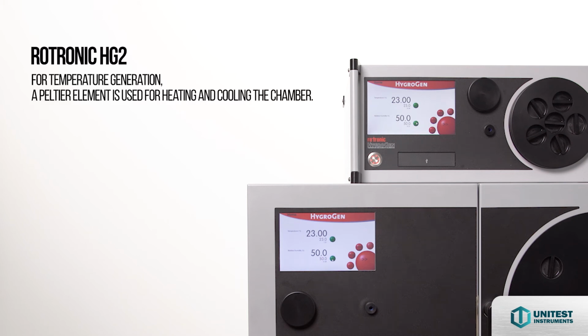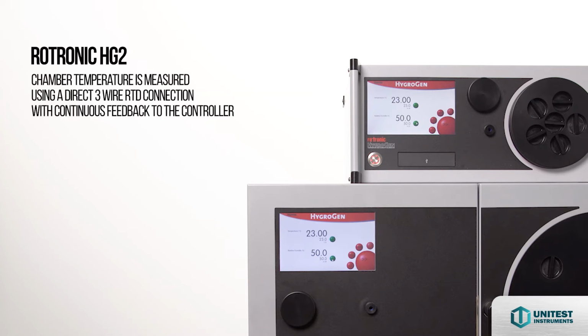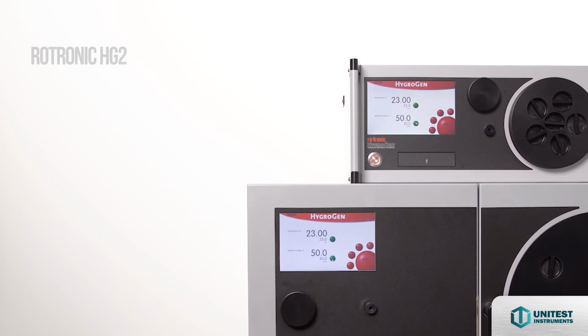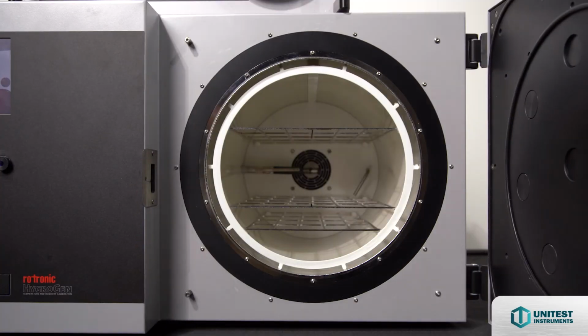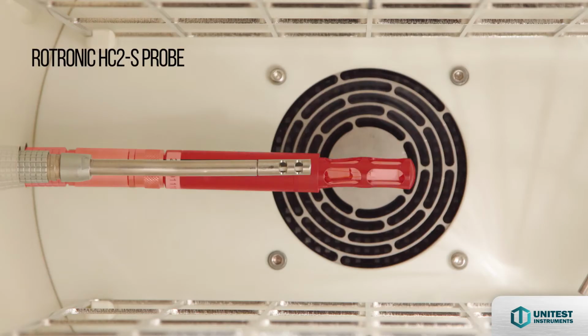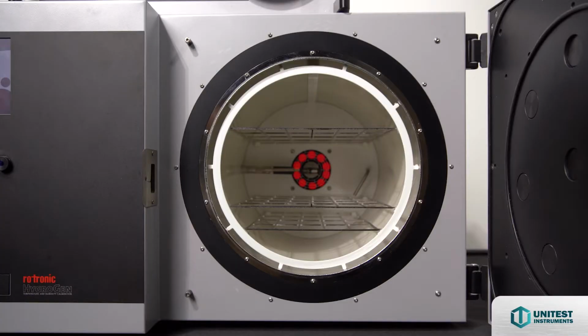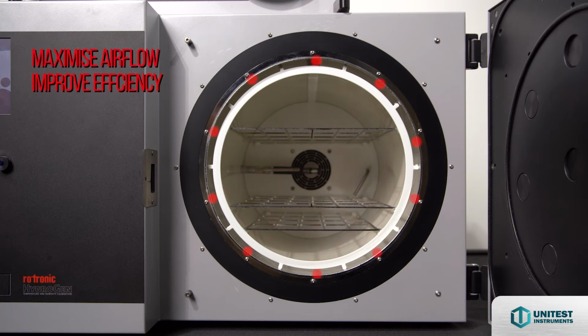For temperature generation, a Peltier element is used for heating and cooling the chamber. Chamber temperature is measured using a direct 3-wire RTD connection with continuous feedback to the controller. Measurement and control is provided by a combination of a Rotronic HC2S probe, an embedded PT100 sensor, and a multi-loop controller. The chamber of the HG2 is also carefully designed to maximize airflow patterns and improve efficiency.